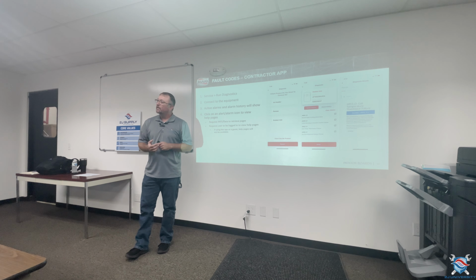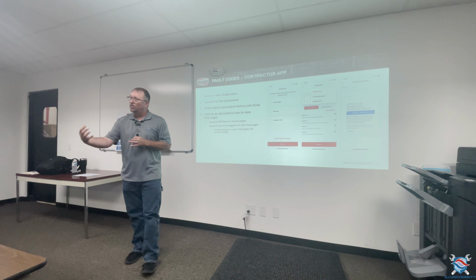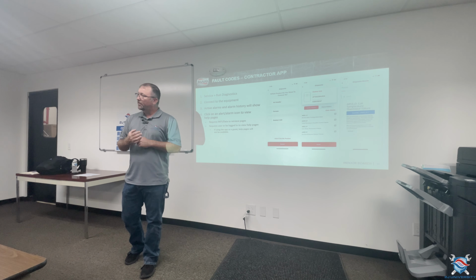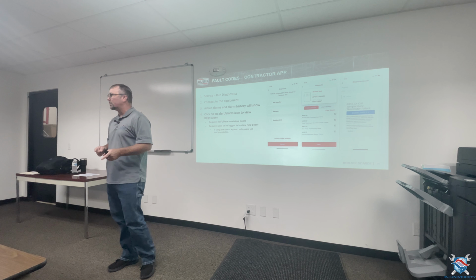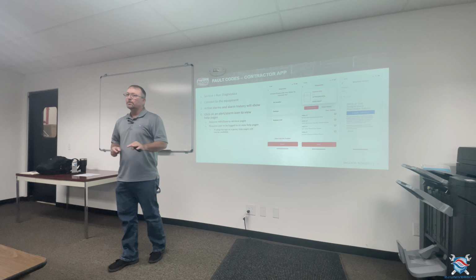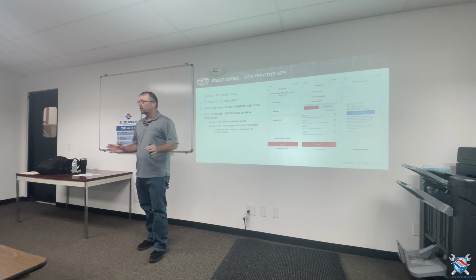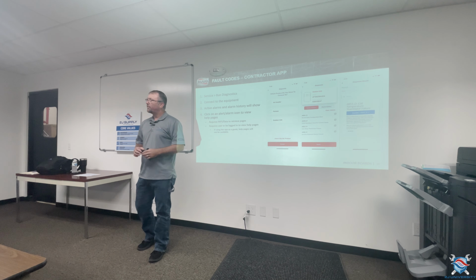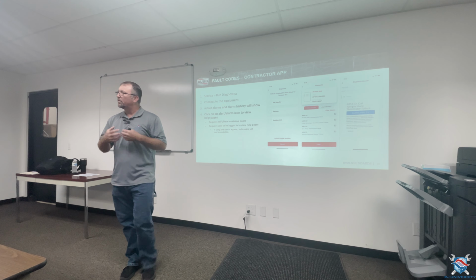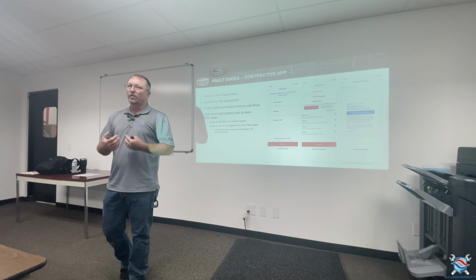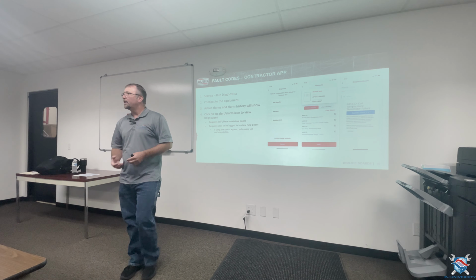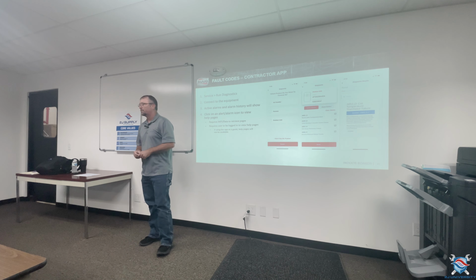And the reason being is because what it's going to do is pull all that data off that old control board. And then when you put the new control board in, it's going to flash the new control board, because the new control boards are universal control boards. They're not flashed with models and serial numbers. You have to physically flash it so it knows what the parameters for blower, high heat, low heat, single stage, two stage are.